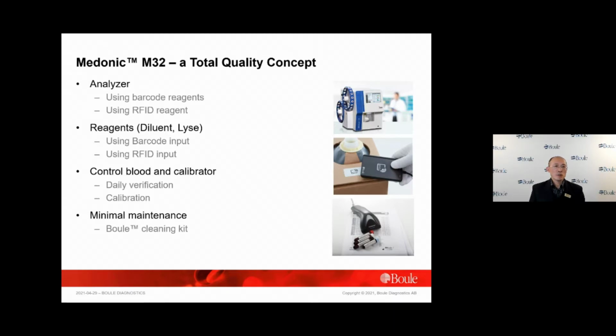Analyzer coming to market in 2 formats. Not hardware, but software configuration. The barcode reagent input and the RFID input type of instrument software have a different article number. For the previous instrument, it is possible to convert from a barcode reagent input type into an RFID reagent input type, not the opposite. So it is possible to order an RFID conversion kit to upgrade the barcode reagent input type instrument into an RFID type.